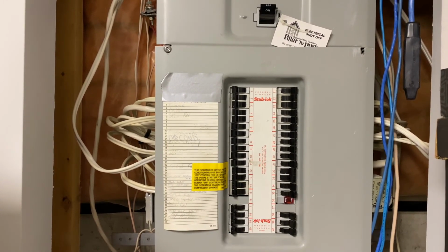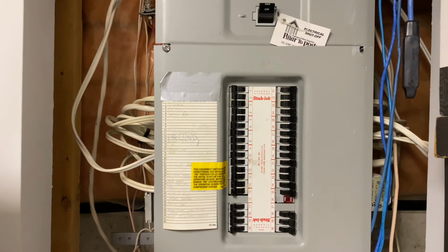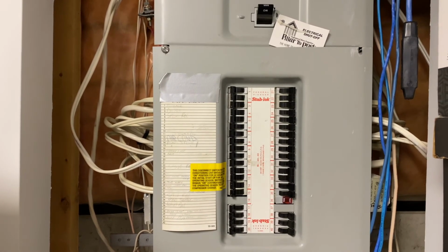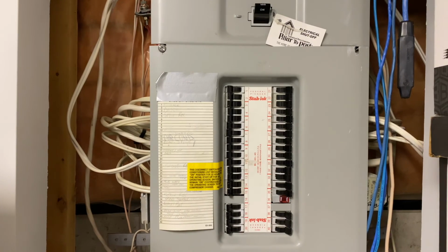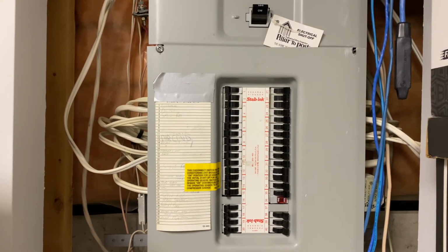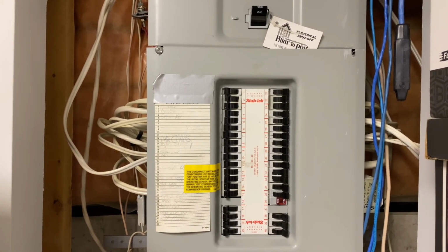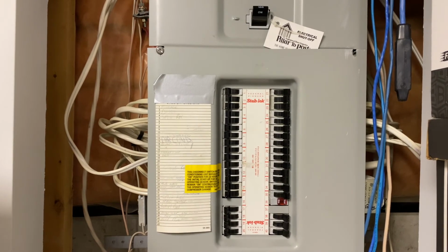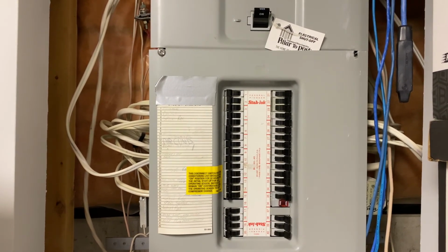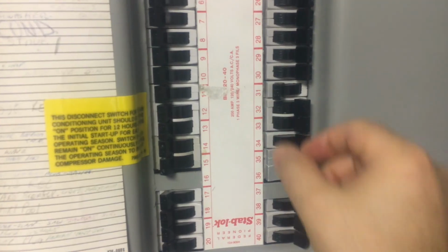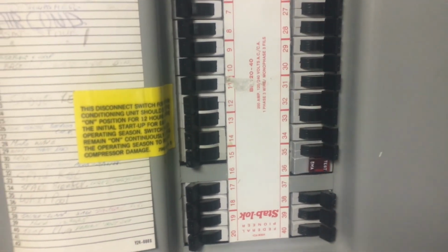That's a signal to you that something's wrong, and you'll need to figure out why so it doesn't happen again. It could be because of too much load, or there might be an exposed wire, or a crossed wire, or whatever. There's a problem. Figure it out and correct it. Then re-enable the circuit by turning it on, like this.